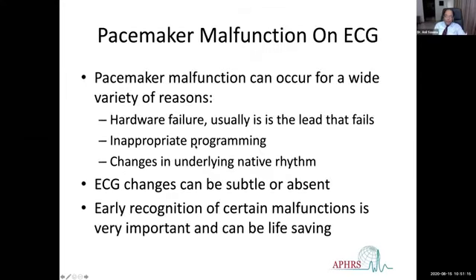Now, pacemaker malfunction can occur because of a variety of reasons. There could be hardware failure, and usually it is the lead that fails. Pacemakers usually don't have much problem. They're very robustly designed, but the lead is the weakest link. There can be inappropriate programming sometimes, or there can be some change in the underlying native rhythm, which makes us feel that the pacemaker is not behaving properly, or sometimes it can lead to a change in the pacemaker function itself.